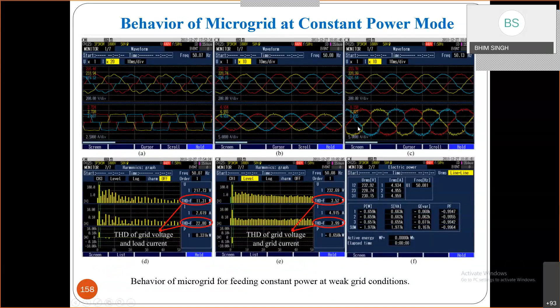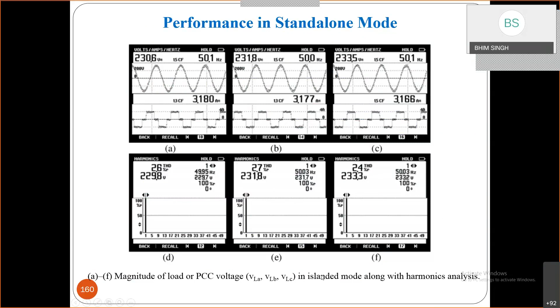Of course, the inverter supplies this despite the non-linearity of the load, also for 3-phase, and we are able to handle all synchronization issues. In islanding mode too, we get quite good THD, 2.7% or 2.67% of the voltage. So even while feeding a non-linear load, voltage is maintained in standalone mode without much problem, working typically as a UPS with solar generation.